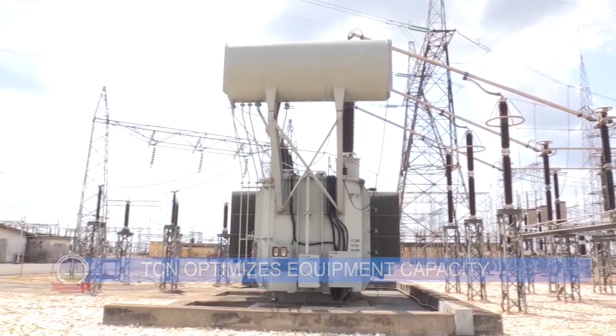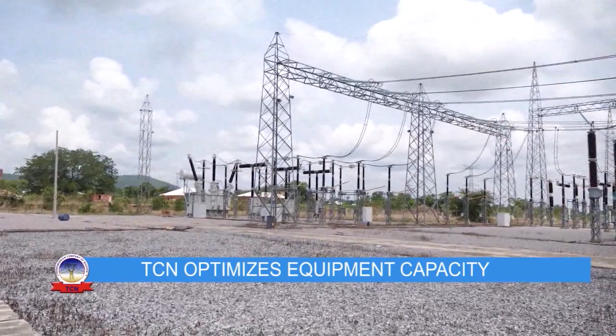By an insulator, it has some dielectric properties that make the transformer safe: not shocking, not conductive, not bursting, not catching fire. So this oil, day 1, day 2, day 3, as the transformer ages, these properties start to deteriorate, and the oil will be getting acidic.